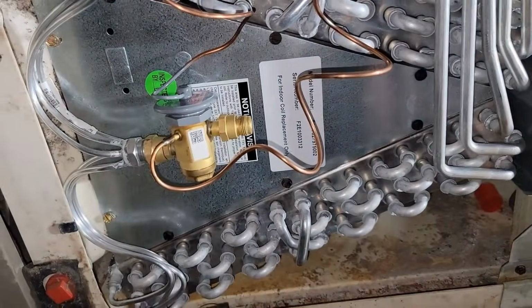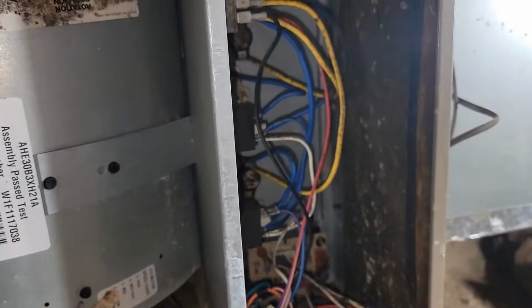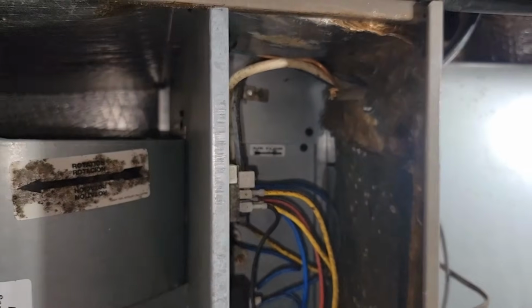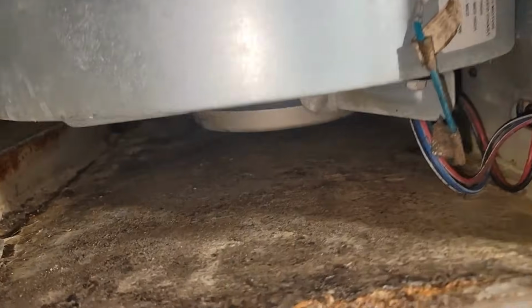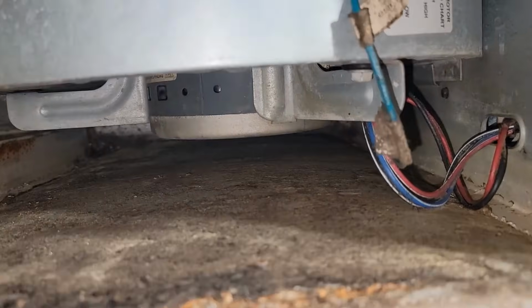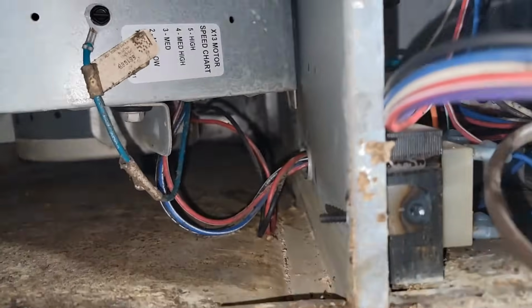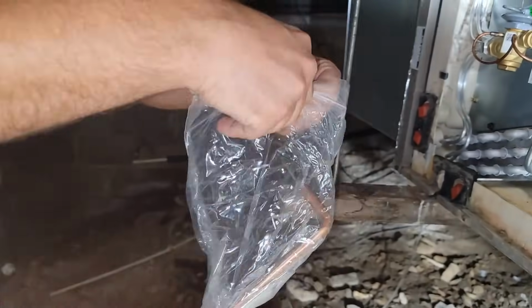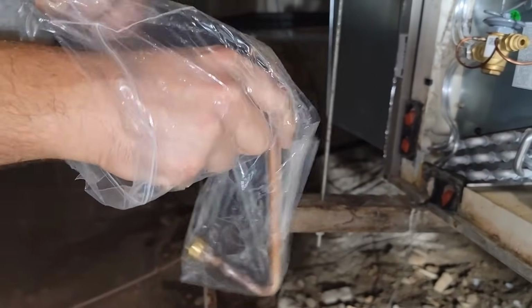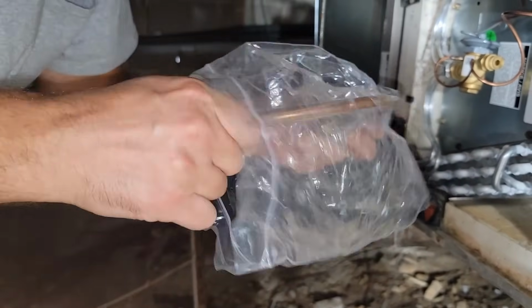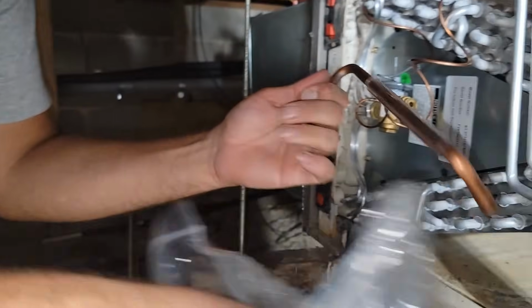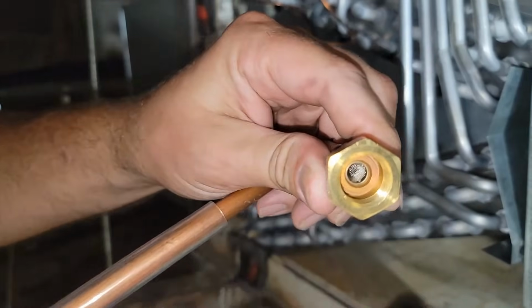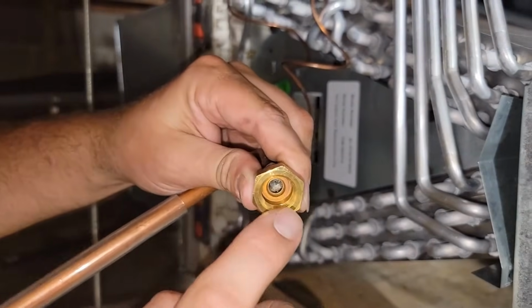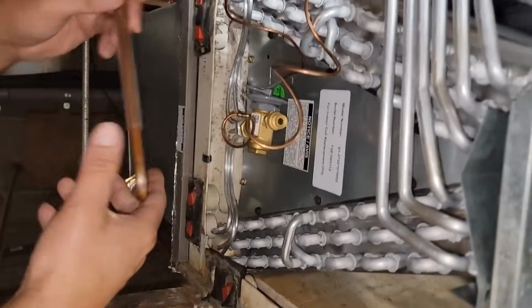New coil, new TXV, got to get the other piece, and then our installation kit, that relay will mount somewhere in here. And there's our X13 motor. See there? All right, here is our 1/4 inch liquid line here. Connects, look at that screen. See that screen in there? Anytime you change a TXV, you need to pull that screen out because that screen could be stopped up.